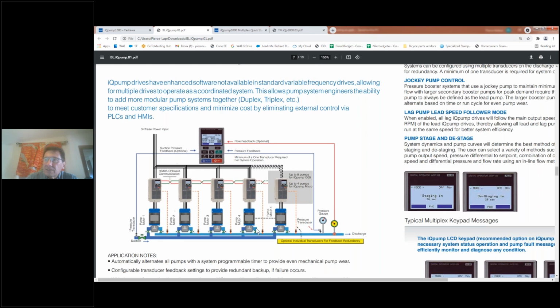So a multiplex system can cost you between 1.5 and 2 times the cost of a single drive, single pump system. And you're going to have to look at that investment and say, are my reliability requirements and my reduction of downtime over the next 10 years worth it? You certainly will get higher reliability and much reduced downtime with a multiplex system.